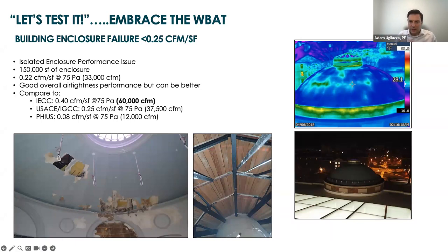The leakage was consolidated to one location, and that ended up being a catastrophic failure. When the mechanical systems malfunctioned, it went into depressurization mode and pulled a lot of cold air into the space. A sprinkler system ended up freezing and causing millions of dollars of damage. So just because you pass the test doesn't necessarily mean you won't have a performance issue. That qualitative analysis is really important as well, so keep that in mind.